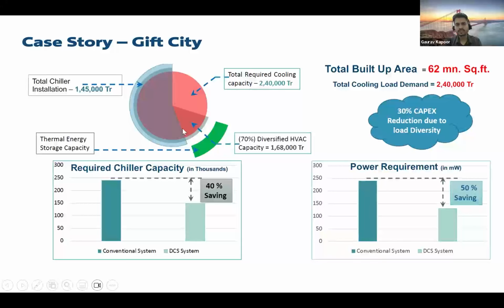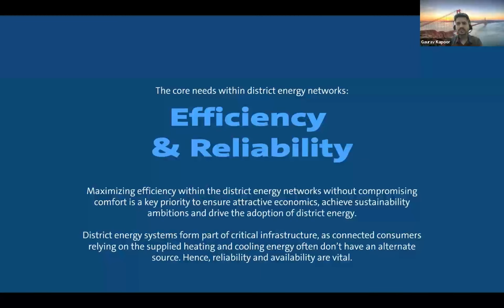Now, by using DCS instead of a conventional system, they reduced the chiller capacity from 240 to 145, which is approximately 40% saving straight away on the chillers. And if we look at the power requirement, which was around 240, it has been further reduced to around 125, that is 50% saving on the electricity. So this case study, which has already been executed within India, clearly showed that DCS is able to save 30 to 40% on the chiller capacity, which further helps you to reduce your refrigerant requirements, leakages and ODP depletions. And it also helps to save around 50% on the electricity when a conventional system is compared to a DCS system.